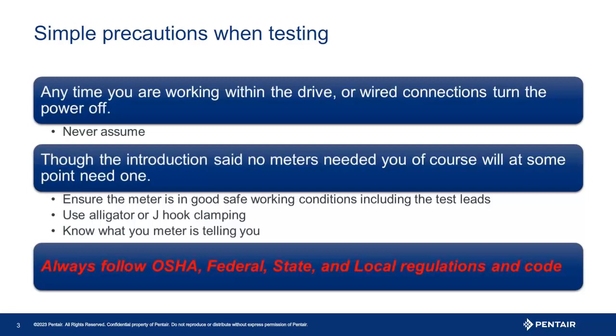Remember safety first. When working within the drive or wired connections, turn the power off. Never assume the drive is powered down. Though the introduction said no meters, we may eventually need to ohm test the motor, for example. Know how your meter works and ensure it is set to read the proper measurement needed. Make sure the probes are connected correctly and in good condition, and use alligator clamps or J-hooks to ensure a firm, hands-free contact. And always work safe, know the regulations and codes, and follow them.